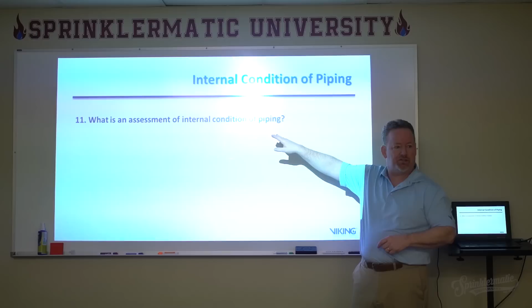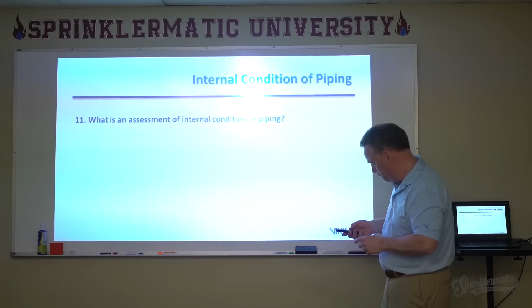We may suspect issues based on the results we get from tests. We may have to pull off the faceplate of dry valves and things like that, or valves, in order to reset them. But that's not the same as an assessment of the internal condition of pipe. What we're looking for here is access to the interior of the piping system to make sure that it's not corroding, or that the corrosion that is occurring, because it will occur. Anytime you have steel, oxygen, water, you're going to get some corrosion. But has it gotten to the point where it is now going to be obstructive? There's going to be obstructive material created that's going to cause a problem with my sprinklers.